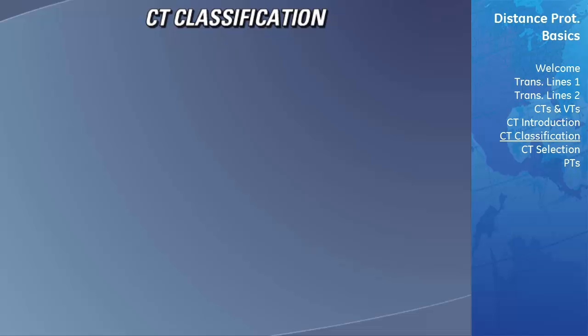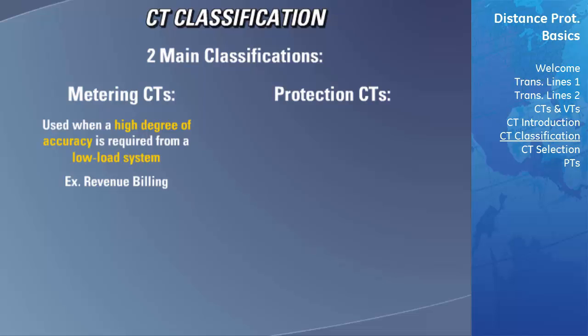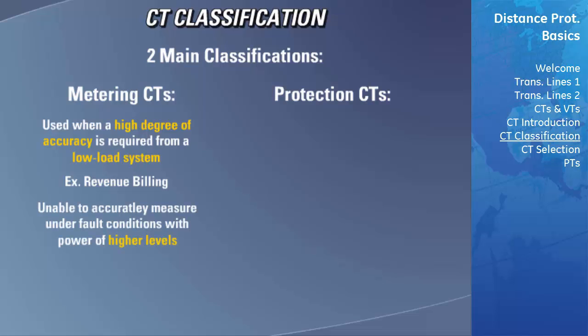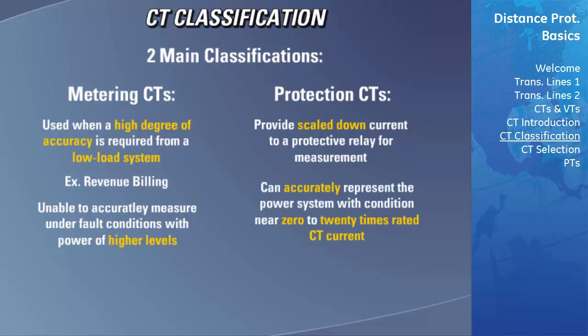CTs are separated into two classifications: metering and protection. Metering CTs are used where a high degree of accuracy is required from low load up to the full load of a system — an example is revenue billing. However, these CTs are unable to accurately measure higher levels of power that would occur under fault conditions. CTs for this function are called protection class CTs. Protection class CTs provide a scaled-down current to a protective relay from conditions near zero current all the way to 20 times rated CT current, with an error percentage commonly ranging from 5 to 10 percent.